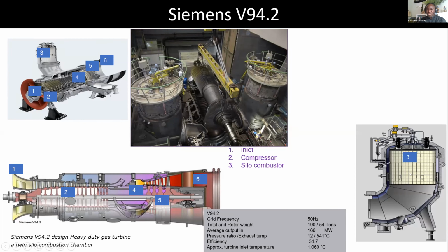So this is typically how the combustion chamber looks. You have the burners at the top, and you have the flame tube with tiles. These are ceramic tiles, which protect the casing of the combustion chamber from the hot gas. Then you have the mixing chamber, which in GE is called the transition piece, which I showed just a little. But you see how huge this is, there are two of them, which more or less narrows the hot air to be able to go into the turbine. And so the hot air coming out of the mixing chamber goes into the inner casing. So here you find the inner casing, and from the inner casing it goes to the turbine.